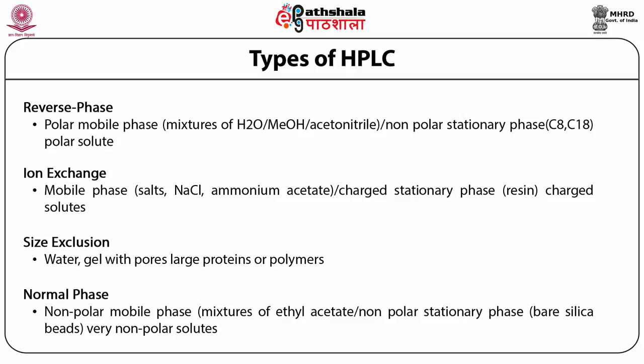Then came reverse phase. The stationary phase was converted to hydrophobic upon which hydrophilic solvents are used. Hydrophilic solvents are water-based solvents miscible in water at any ratio — water, methanol, and acetonitrile are used in most reverse phase applications. The stationary phases are predominantly silica-based but surface-modified with non-polar carbon chains like C8 or C18. Sometimes the surface is modified with a phenyl ring, giving different column chemistries.